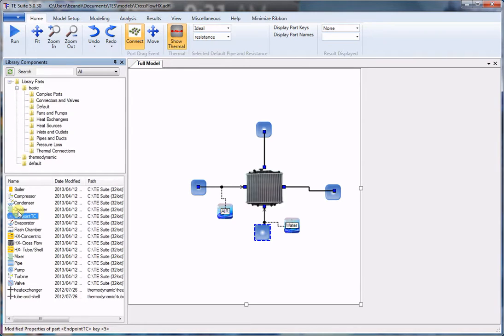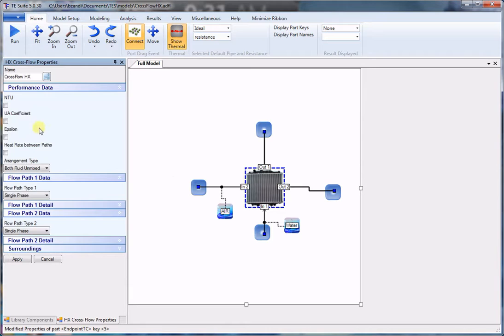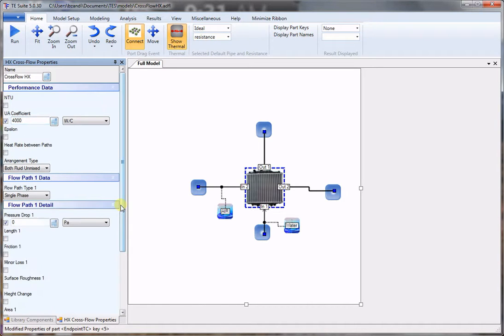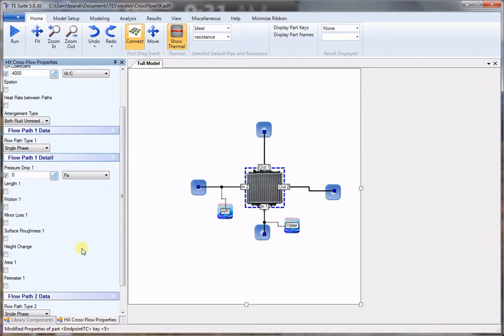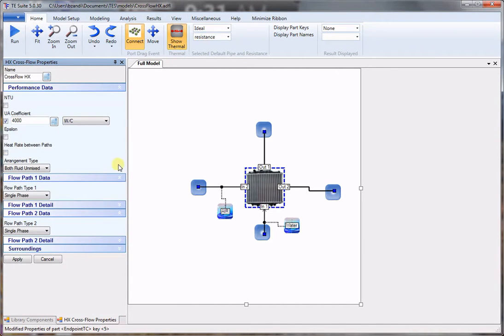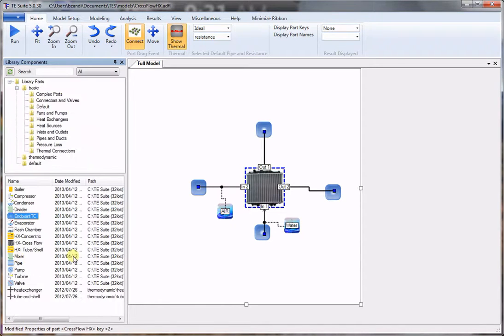Now we double click on the heat exchanger to set its user properties. We leave NTU unchecked — it will be calculated. UA is the product of heat transfer coefficient and area, so that would be 4000. Epsilon will also be calculated. If you wanted to add some losses, you click on it and can enter the values. Everything else is left unchanged.